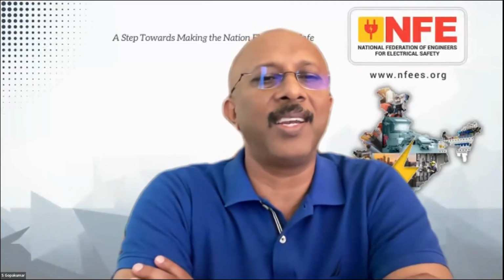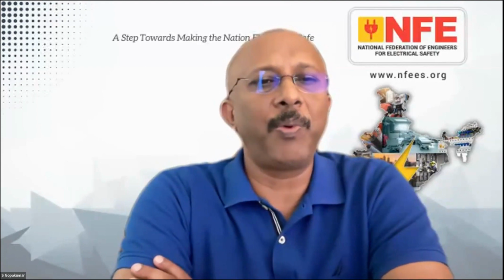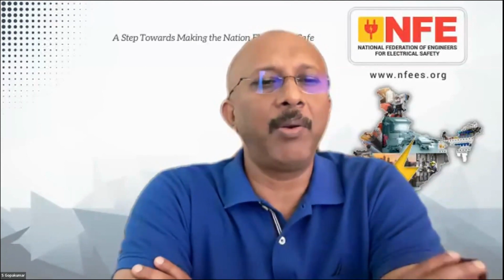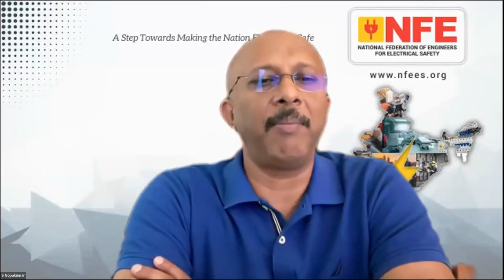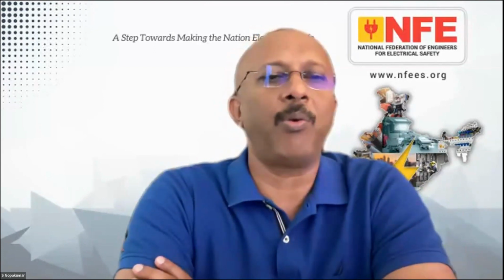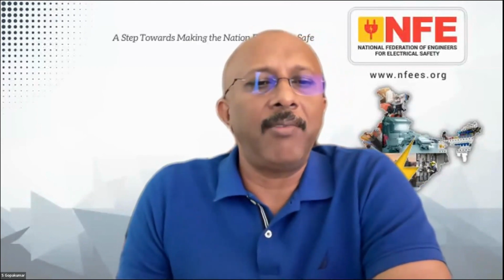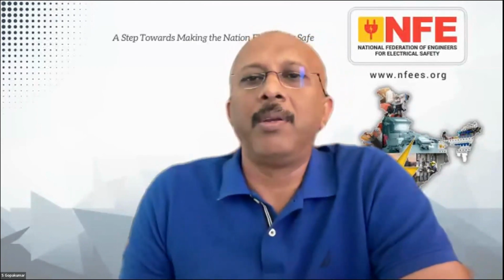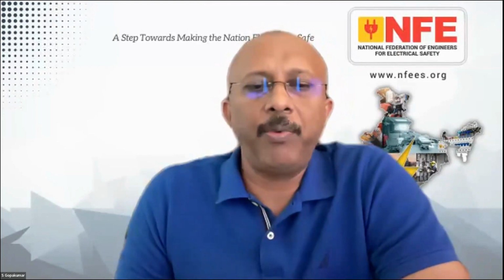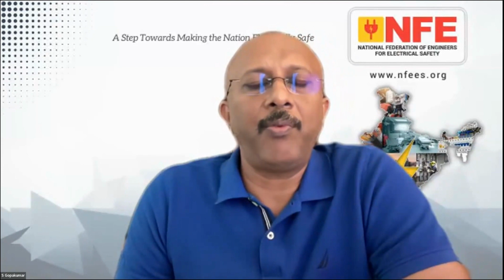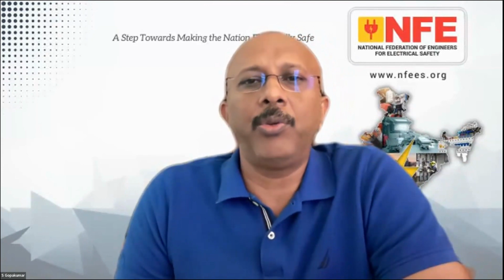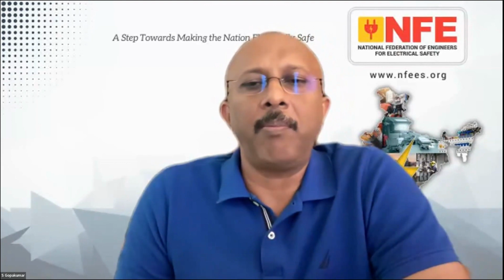Okay, I'm not entirely sure about the construction. If the standards allow to do this, then yes. I will answer this. The practice in India is a little bit different from other countries, because in Europe you use an armored cable once when there is a chance of mechanical damage, whereas we use it everywhere, for example, in industries inside the factory, inside the premises also. So if we look at the standard point of view, the IS 3043, we cannot very clearly say that the standard allows to use armoring as a fault return path.